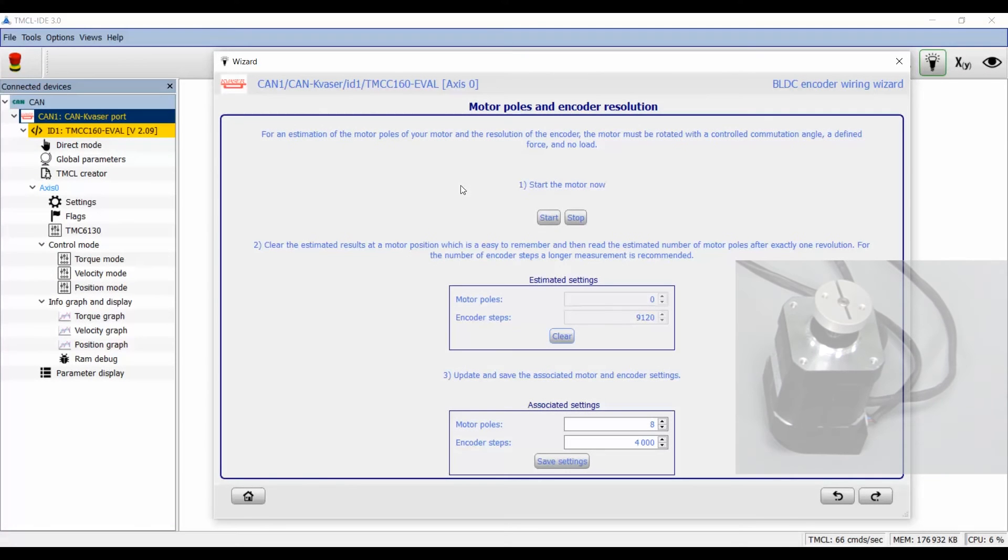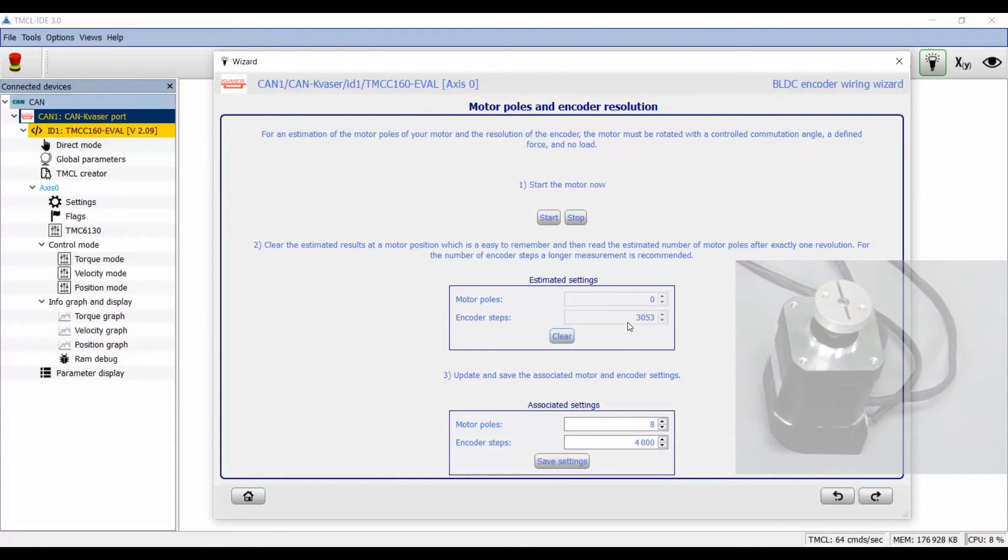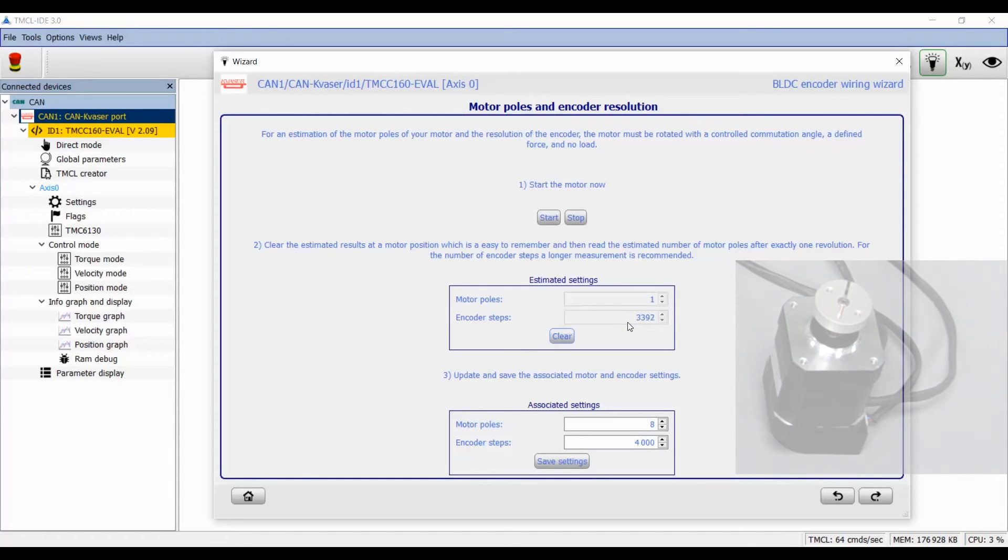In the next step I use the open loop mode to check the motor pole count and the encoder resolution. Therefore I start the motor with a slow velocity and read out the motor pole count after exactly one rotation. For better accuracy of the estimated encoder resolution, it is better to rotate the motor several revolutions.